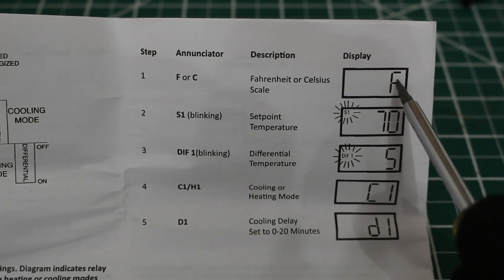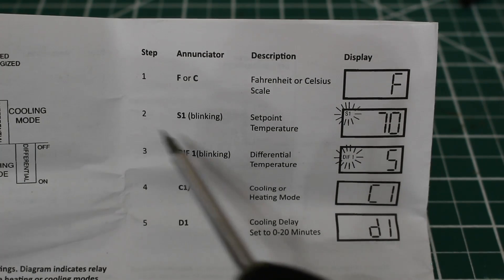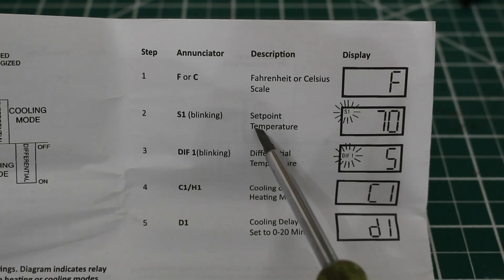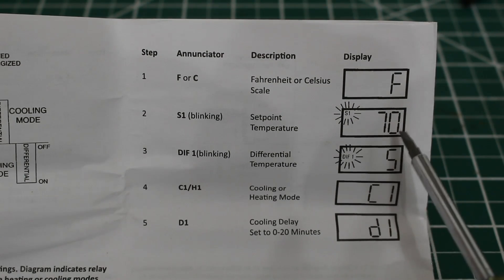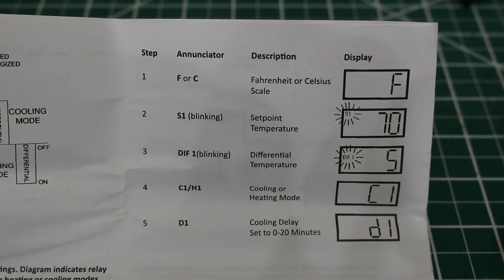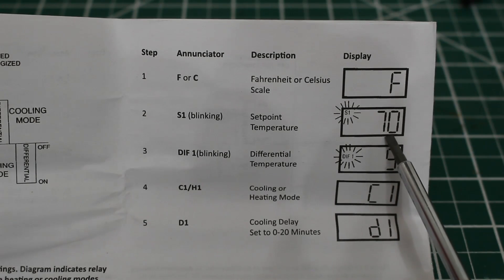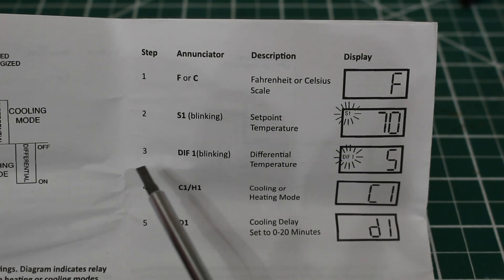Then we're going to click Set once again and move into step two. You're going to see S1 and it's going to be blinking — this is your set point temperature. So let's say this is a refrigerator and you want it at 37 degrees. You're going to set your set point to 37 degrees. This is the temperature you're going to be maintaining. Click Set and you're going to move on to step three.